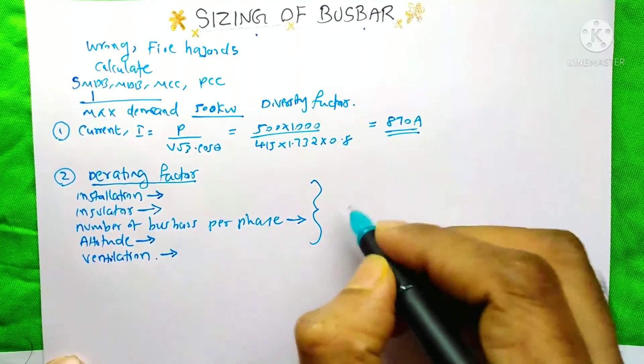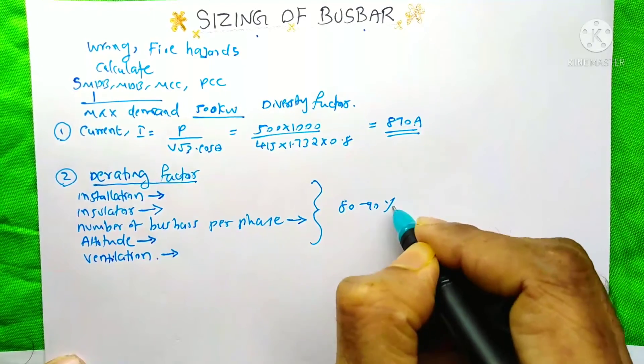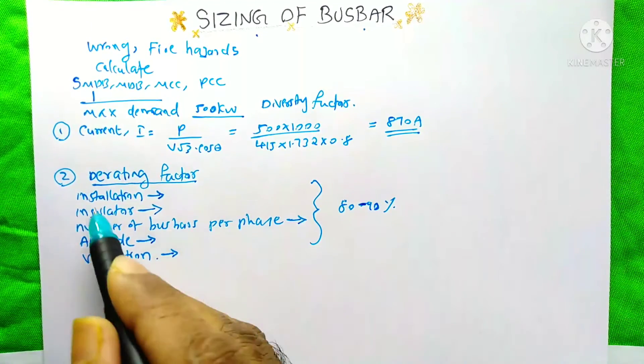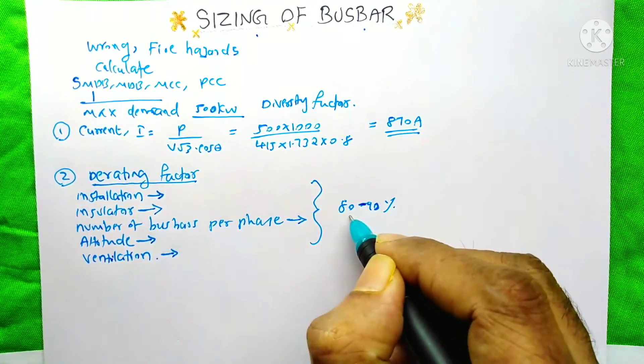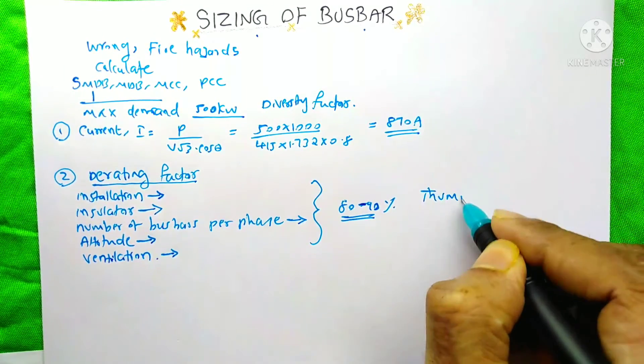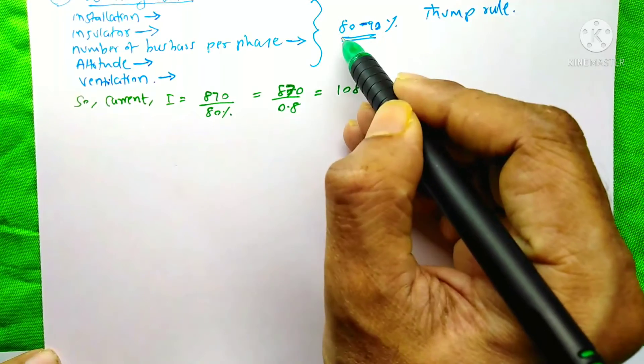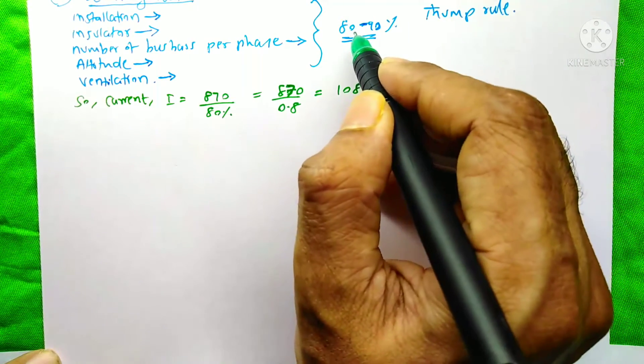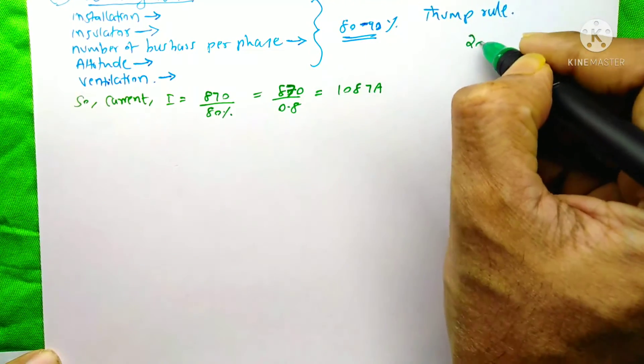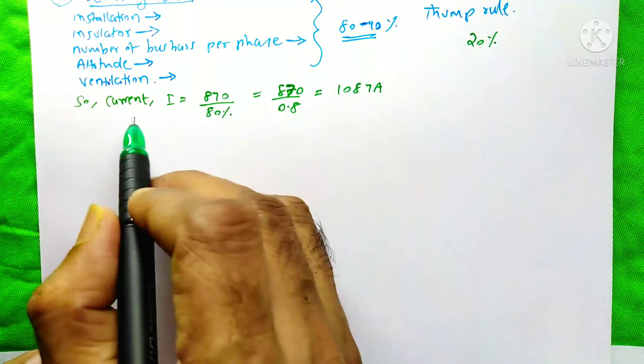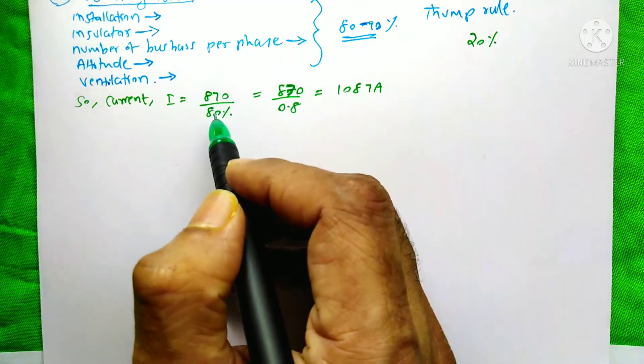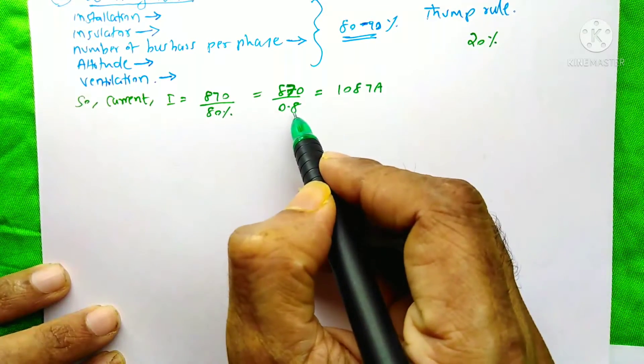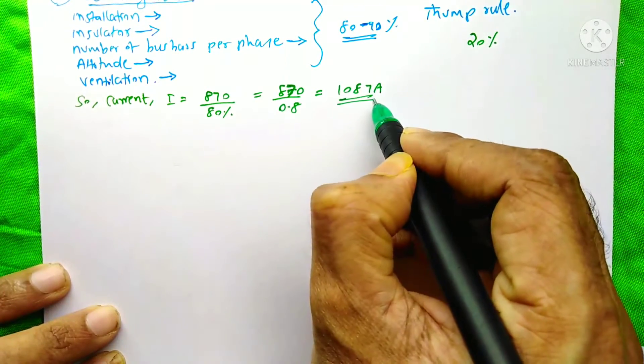In industry, we generally take 80 to 90 percent as the derating factor. Without going through the detailed table, this is a thumb rule. Suppose our derating factor is 80% — this means the bus bar provides only 80% of its rated capacity, so 20% is lost. To compensate, we divide the current by 0.8: 870 / 0.8 = 1087 amps.